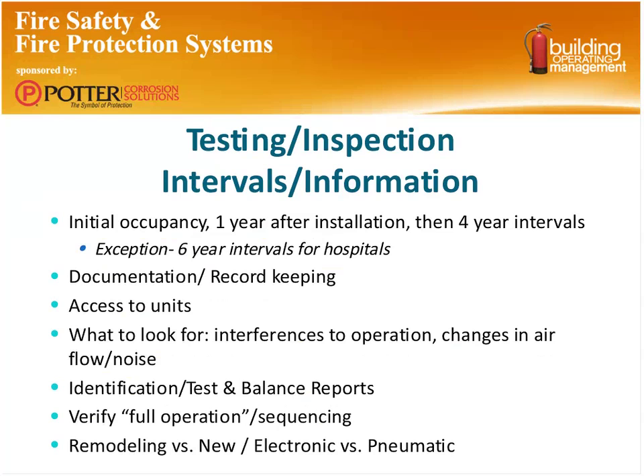So what kind of testing and inspection are we looking at? What kind of intervals and what kind of detail should you be looking for when you're trying to get this service taken care of within your facility? Well, initially, NFPA 80 and 105 require inspection and testing 1 year after installation. Then it moves to a 4-year interval after that initial year. The only exception to that is hospitals, which move to a 6-year interval for testing and inspection. And when we say testing, we have some local authorities in our areas that require an annual visual inspection.